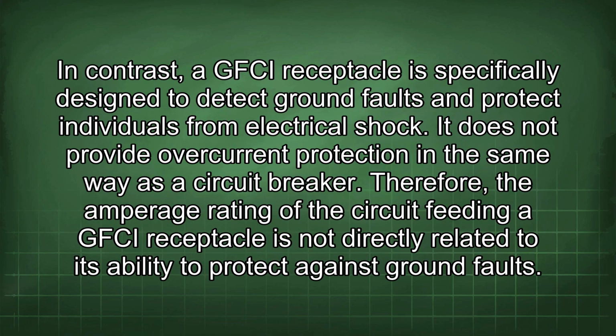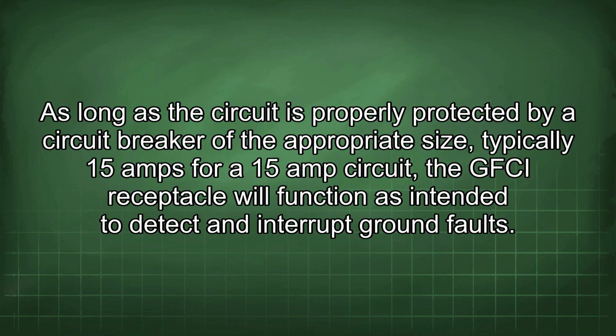In contrast, a GFCI receptacle is specifically designed to detect ground faults and protect individuals from electrical shock. It does not provide overcurrent protection in the same way as a circuit breaker. Therefore, the amperage rating of the circuit feeding a GFCI receptacle is not directly related to its ability to protect against ground faults. As long as the circuit is properly protected by a circuit breaker of the appropriate size, typically 15 amps for a 15-amp circuit, the GFCI receptacle will function as intended to detect and interrupt ground faults.